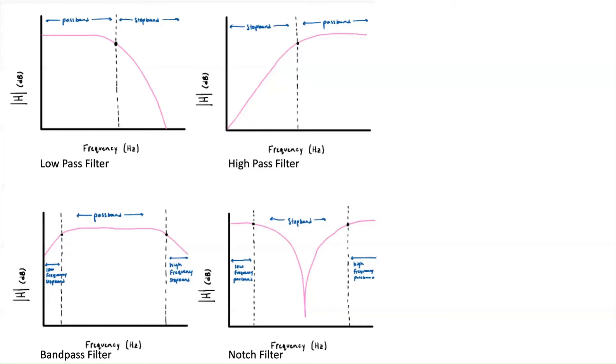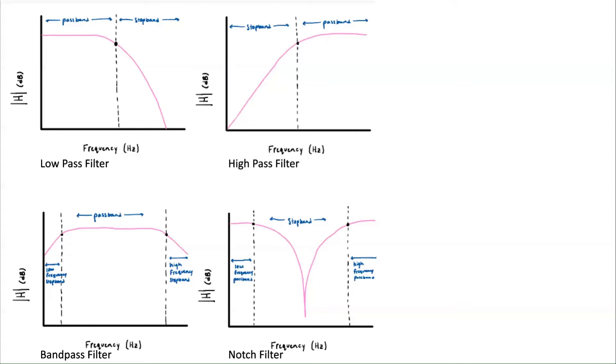Many pacemakers include low-pass and band-pass filters to more clearly read the cardiac signal inputs and remove unnecessary signals from outside noise, such as surrounding muscle movements and even signals found outside of the body. This allows for effective treatment of various cardiac conditions with the implanted pacemaker and can be applied specifically to the needs of a patient with strategic selection of a cutoff frequency.